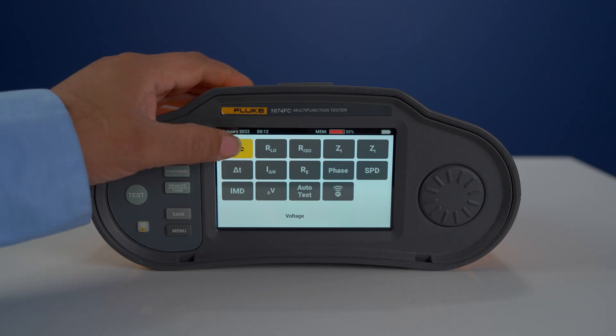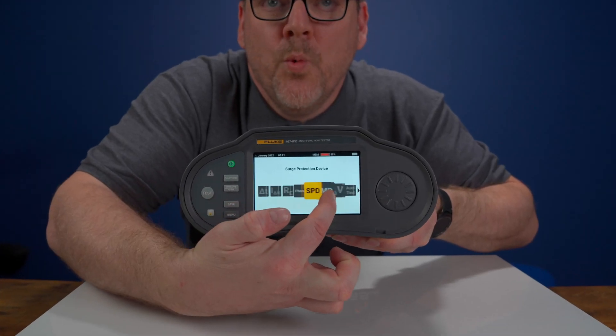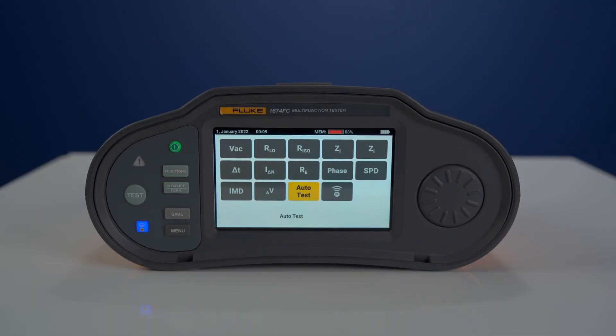Now let's break down the model variations. First, let's look at the 1672. The 1672 can measure voltage AC and DC, continuity, insulation, loop no trip, loop high current, RCD trips, RCD ramp, phase rotation and voltage drop. The 1673 FC has all the functions of the 1672 with the added bonus of auto test, Fluke Connect and EV testing.